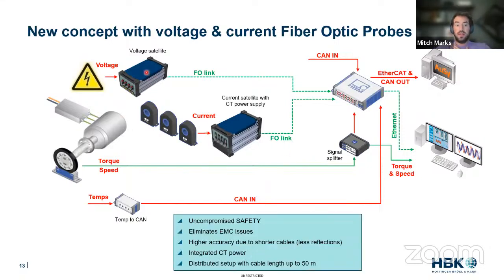So what does this do? What does giving us these fiber optic boxes right next to the measurement do? Well, it gives us uncompromised safety. A fiber optic link has no copper connection. This means there's no high voltages coming back to your control room, coming back to your instrument, interacting with other cables. So this is really as safe as it can get. This eliminates EMC issues, short cables, lower capacitance, less proximity to other high voltages, less proximity to EMC. This is really going to cut down your noise, cut down your headaches, cut down your troubleshooting.